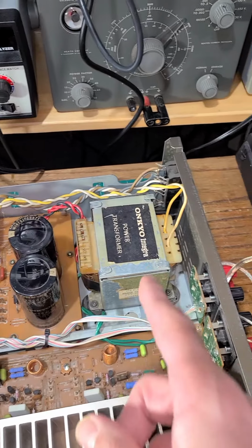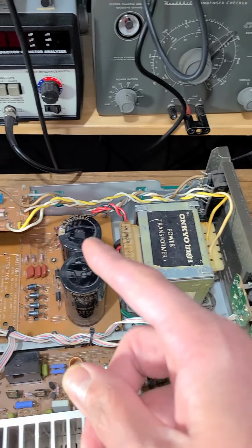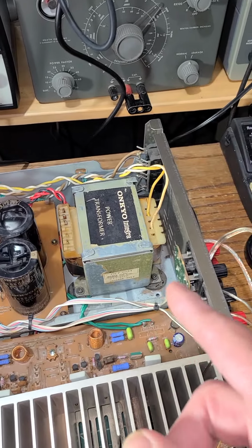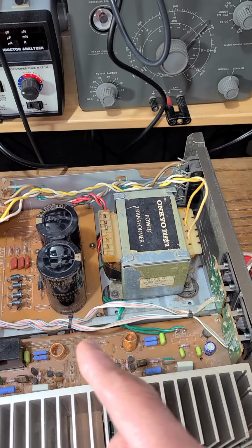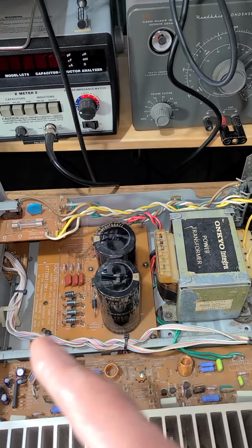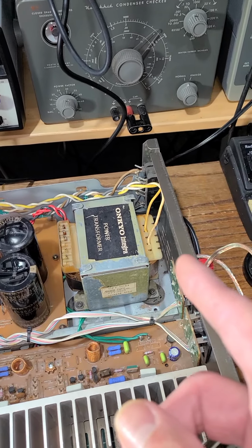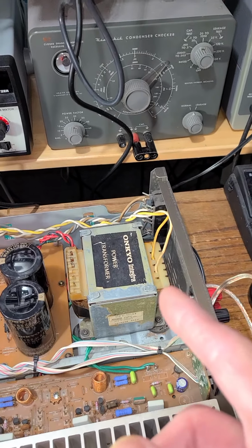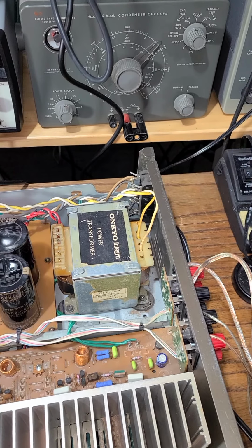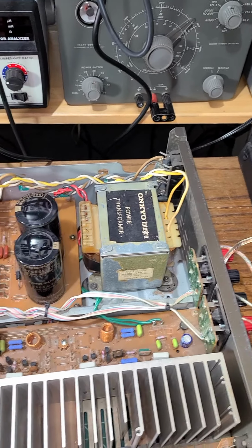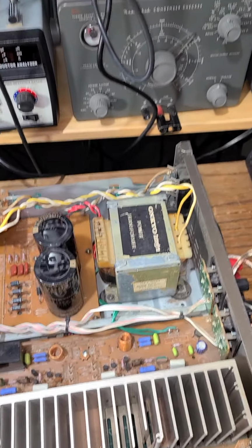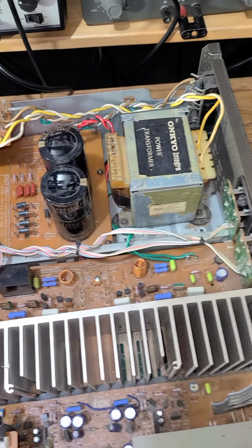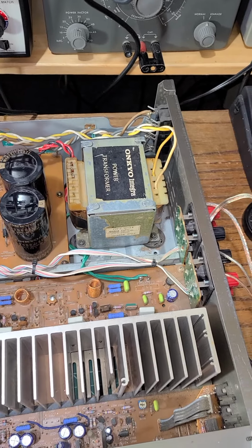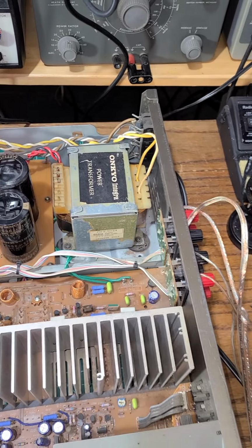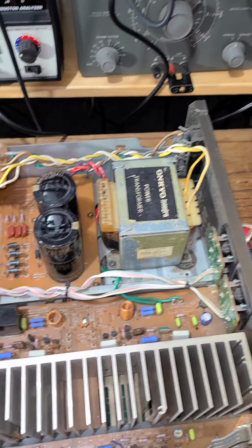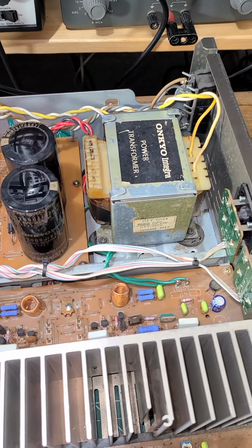So I had no choice. I pulled out this transformer, removed all connections, and checked the windings. The secondary windings tested okay, but the primary winding was indicated to be open. That wasn't good. My first thought was to just toss out the transformer and leave the unit for parts, or for a future fix once I could secure a replacement transformer. I did some searches, but couldn't find any compatible transformer available.